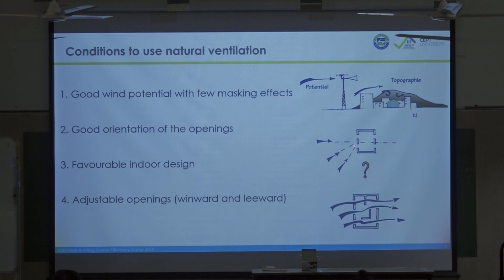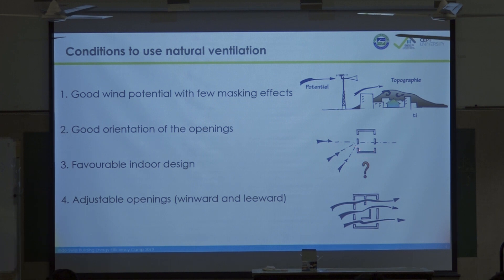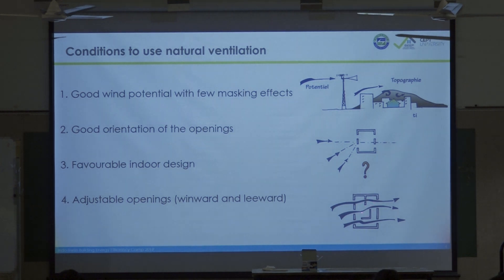You always have a high pressure windward and a low pressure leeward; this difference of pressure generates air velocity inside the building. If the wind direction is parallel to the openings it won't work. Indoor design has a strong effect because you can generate air friction, so all the openings inside the building must be perpendicular to the airflow — you have to have porous walls inside; you don't have to block the air.